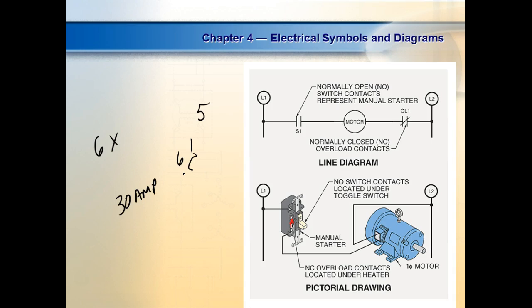Here we go. So here's the stator of a single phase 3-speed motor. So it's going to have a lot of wires coming out of it. Looks impressive, but each wire would give us a different speed. And then it's a capacitive start motor, so it's got 2 wires for the capacitor. Now this has an overload built into it. This is a single voltage motor. It's got an overload built into it. And so here's the overload in this motor right here.